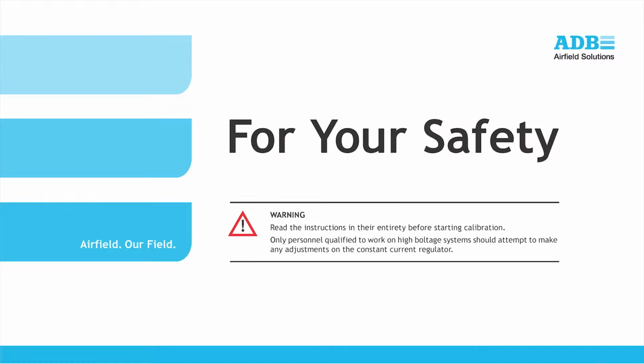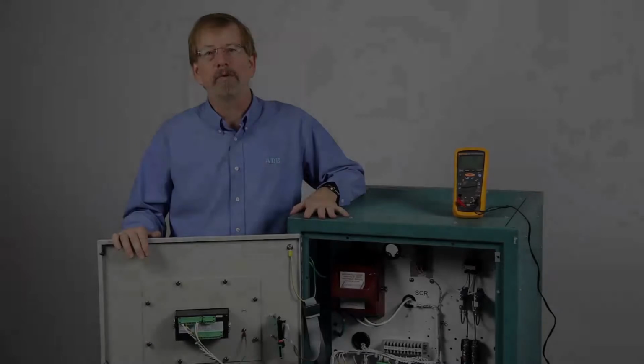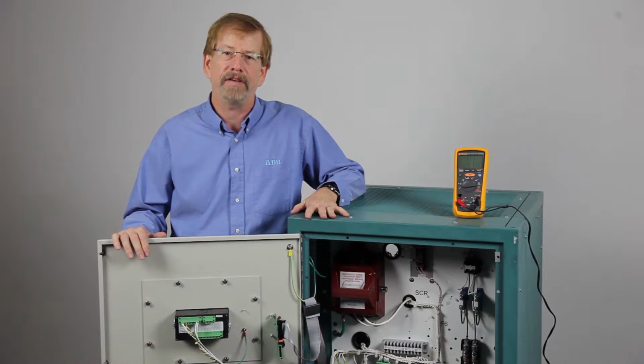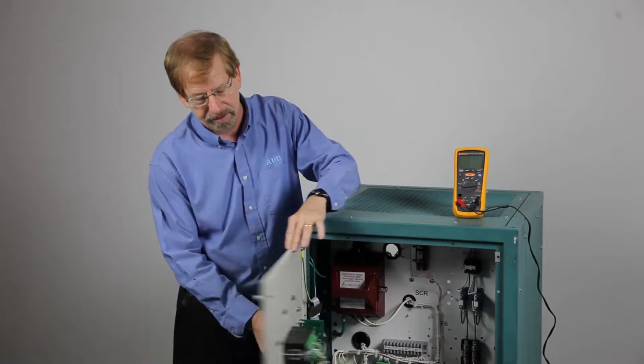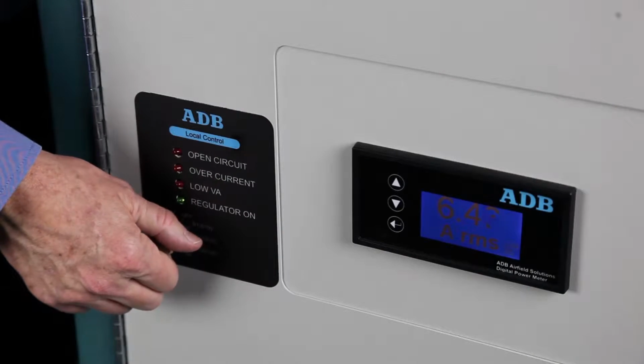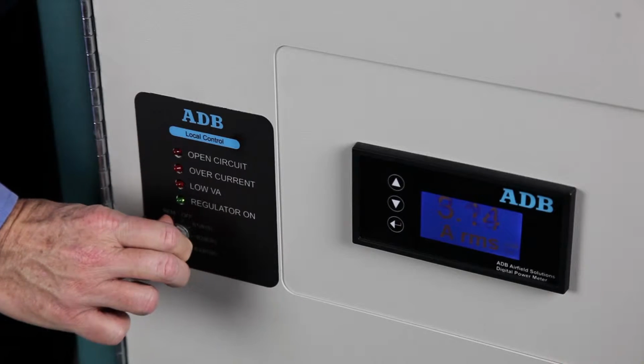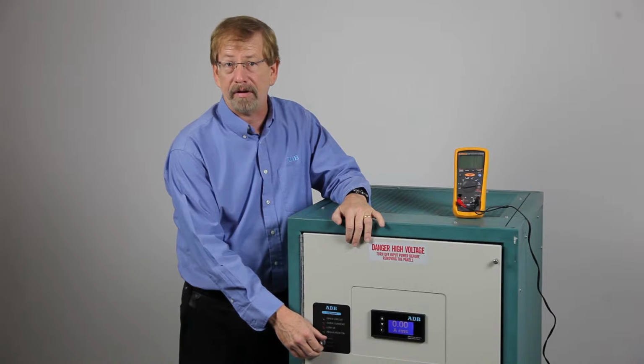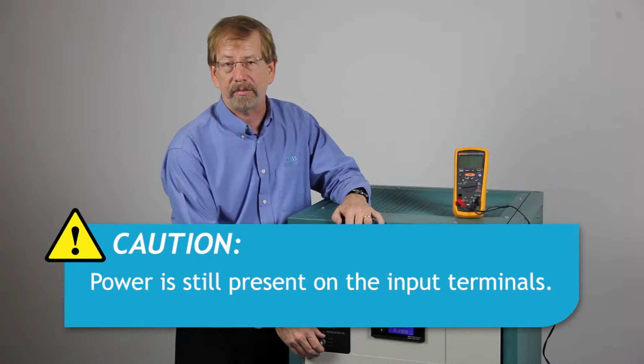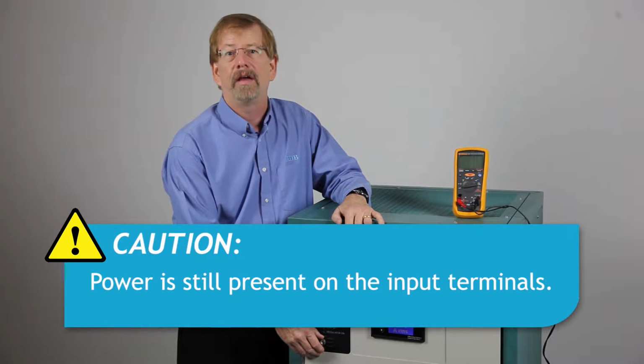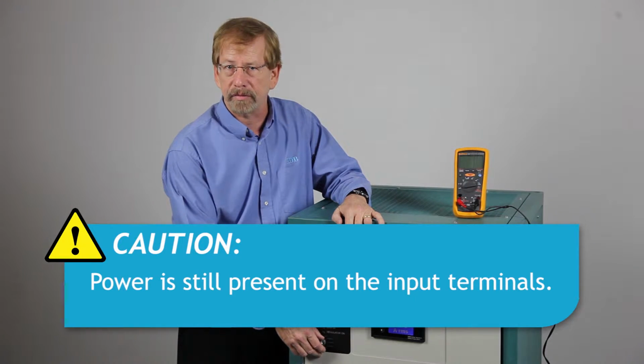Before we begin the calibration, first a safety warning. Read the instructions in the manual in their entirety before starting calibration. Only personnel qualified to work on high voltage systems should attempt to make any adjustments on the constant current regulator. Next, we want to turn the constant current regulator off. If the CCR is in the local mode, take the rotary switch and set it to the off position. This switches the regulator off, but keep in mind that voltage is still present on the input voltage terminals and also on the internal control circuitry within the regulator.